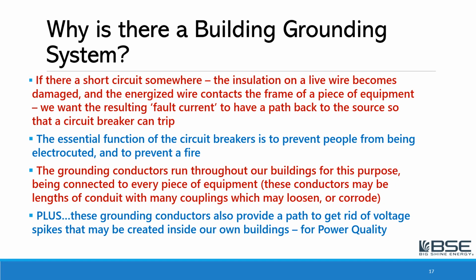But the grounding conductors run all throughout our buildings for this purpose, and they're connected to every piece of equipment. Now, some branch circuits and some buildings, they don't have copper conductors running with the power conductors for ground. Sometimes they use conduit for the grounding circuit. And then when there's conduit, these are like long, thin lengths of pipe, steel pipe, and they have couplings.